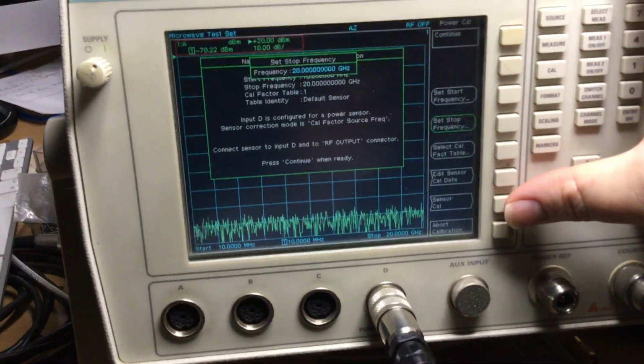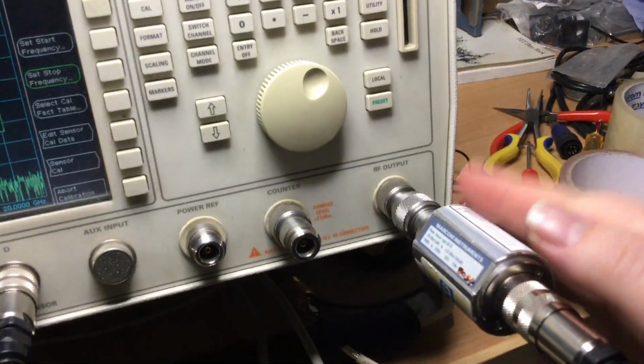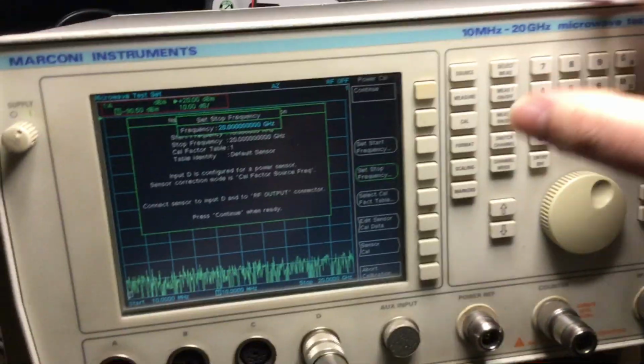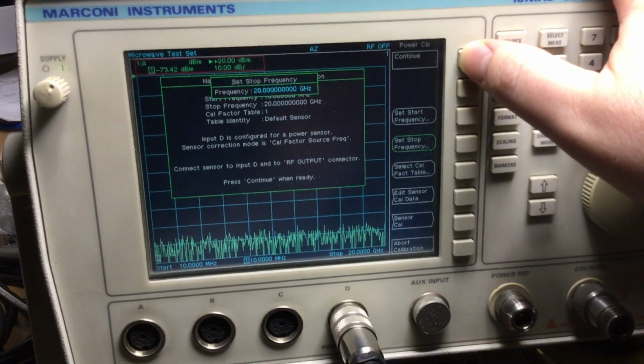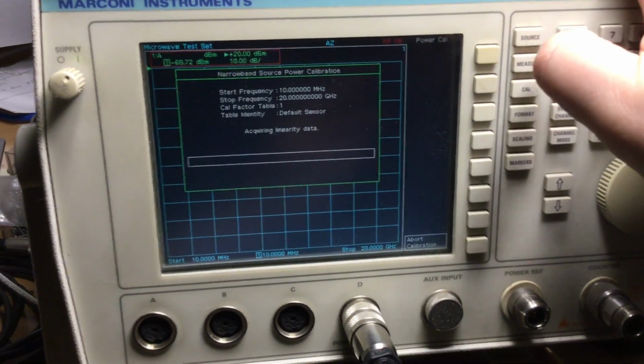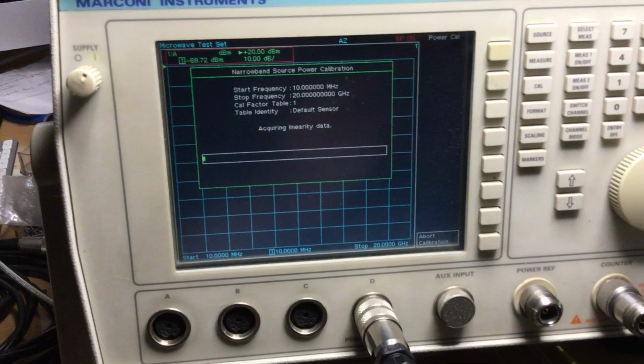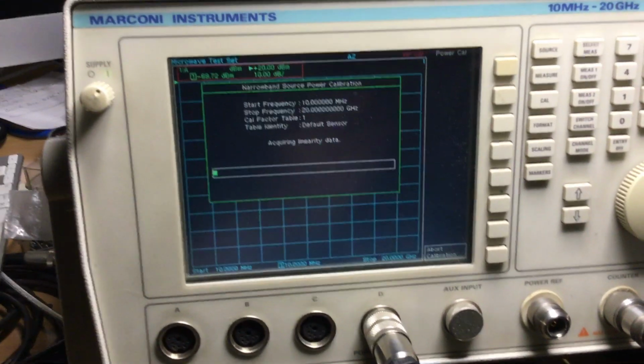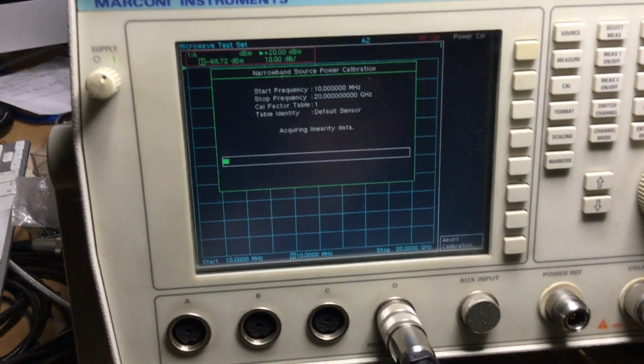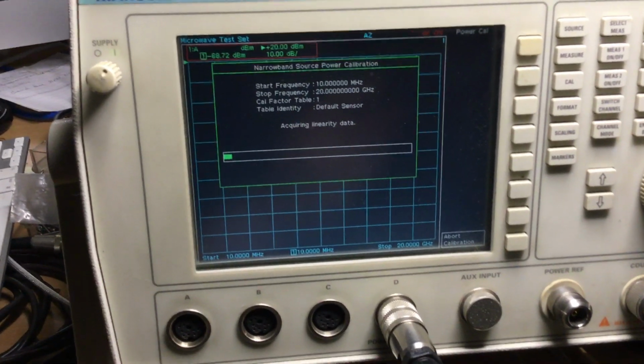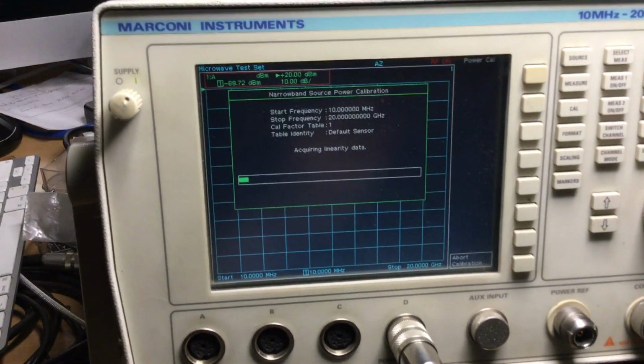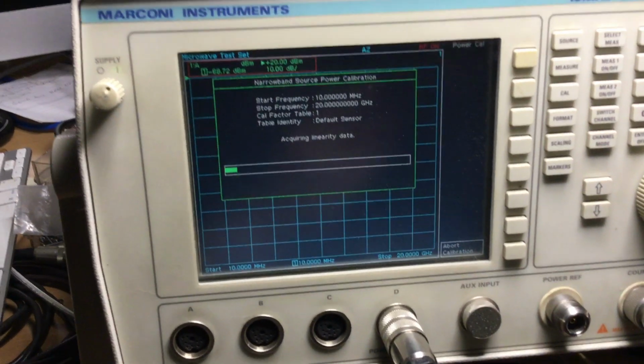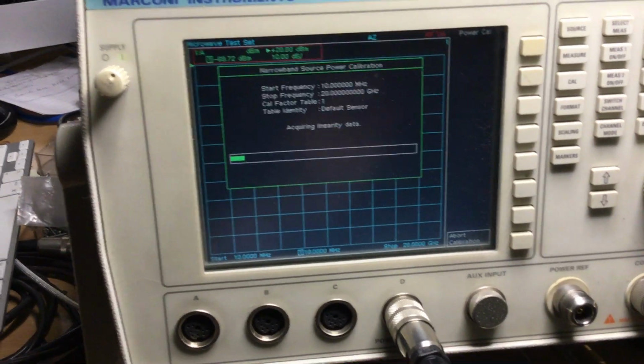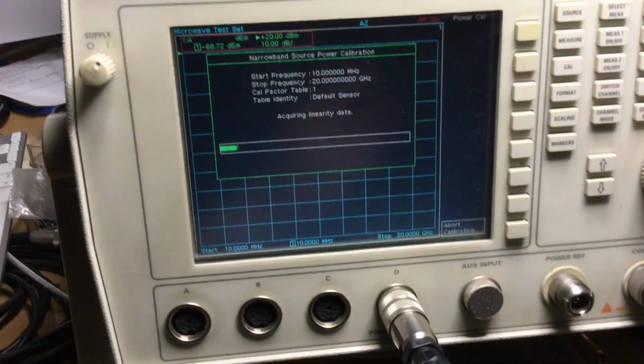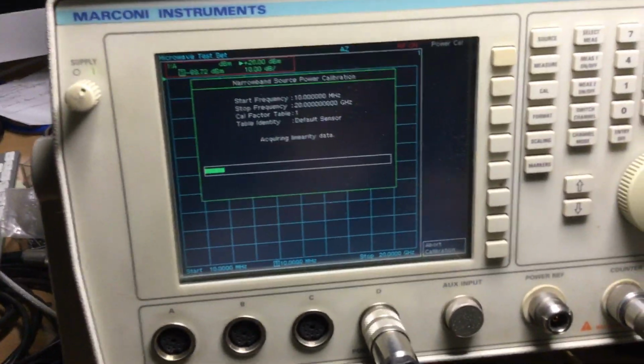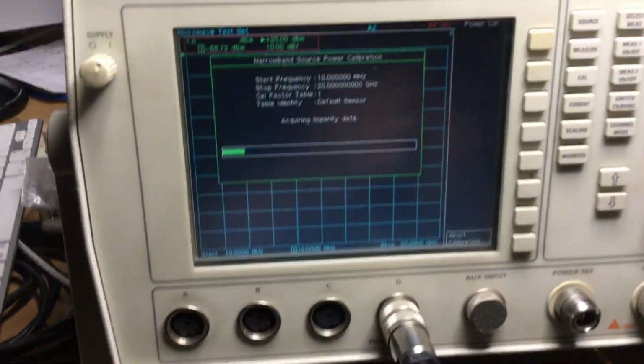You can calibrate the sensor. We've already done that. The sensor's on the output now, ready to read the level coming out, and then all we do is just press continue. Now it's going to try and acquire the linearity data from the sensor. It will read the pick-off diode level, which we've just tried to repair, and then try and calibrate that level at multiple spot frequencies from 10 megahertz to 20 gigahertz, and it'll try and do that as best it can.